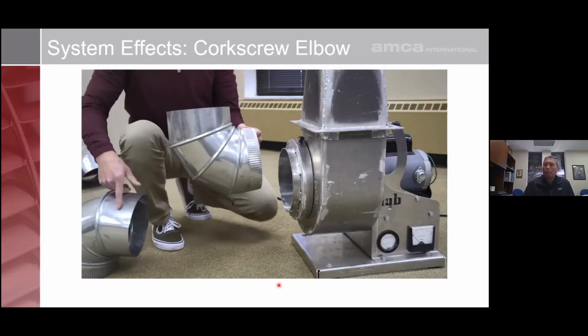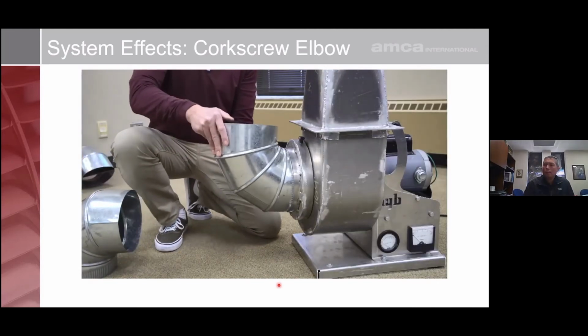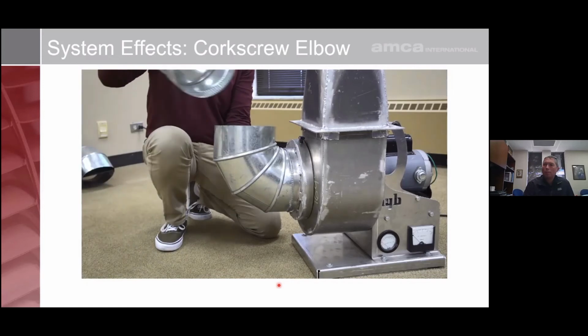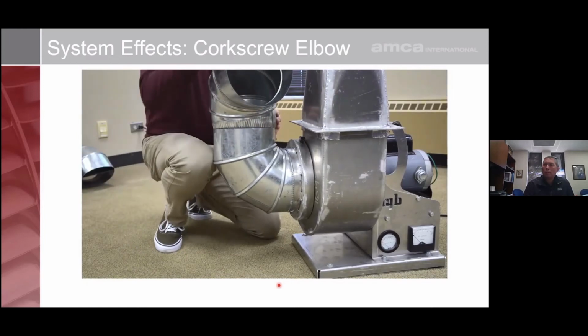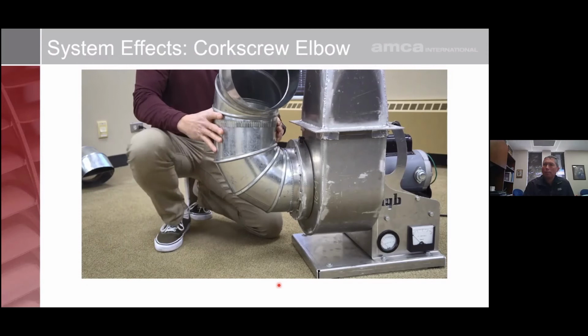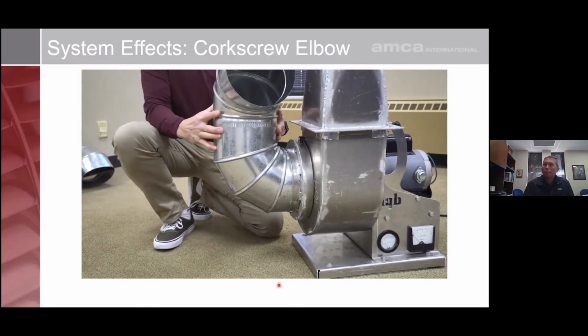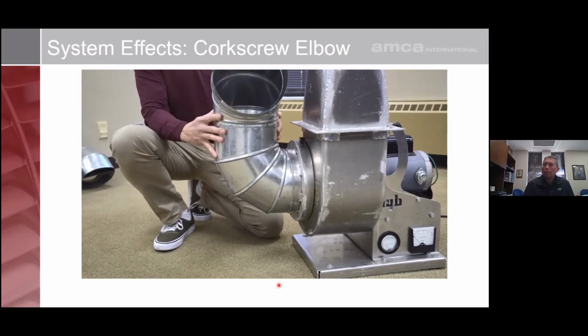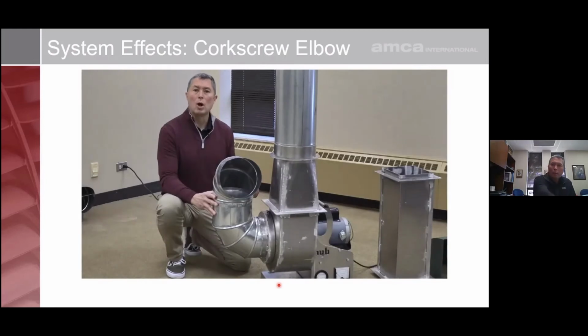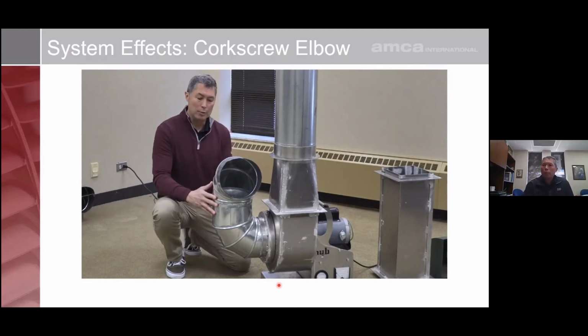So put a 90-degree elbow on the inlet of the fan, and we're going to put it on in this direction here. Now basically, when you're looking at this, you have to also listen to it audibly, because what you're going to hear is either the vibration and the fan noise go up or down. Now in this case, air is coming in this direction.